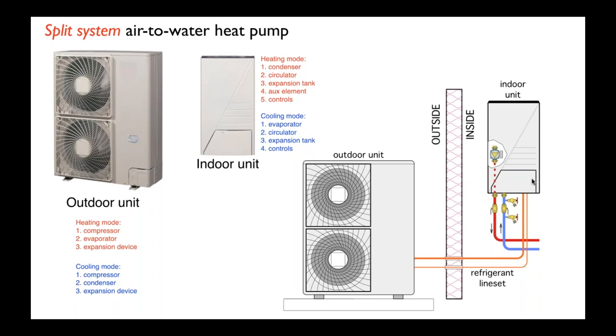Some of these have circulators built in. Some of them have other ancillary items like a pressure relief valve built in. Some of the controls are usually located in the indoor unit. And just to give you an idea, it's roughly the size of a small wall-hung boiler. And you'll see there's a couple pipes coming out of the bottom down here, and these would go off to the balance of system. So fundamentally, we have monobloc systems, self-contained. We have split systems. In a split system, you have the advantage that there's no water in the outdoor unit. So you don't really have to use antifreeze, assuming it's not needed in the balance of the system.